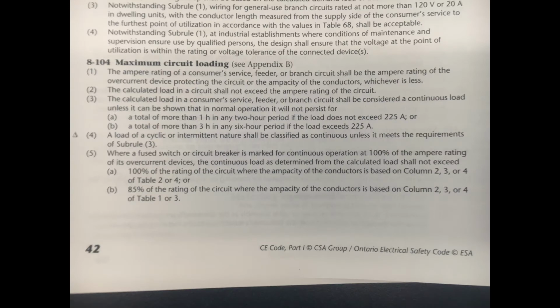Available load. This is the absolute max load on a circuit. For a 15 amp circuit, that would be 15 amps. Max recommended circuit load. Let's look at the code. 8-104 section 1 says, the maximum ampacity will be either the ampere rating of the circuit breaker or the maximum ampacity of the cables, whichever is less.